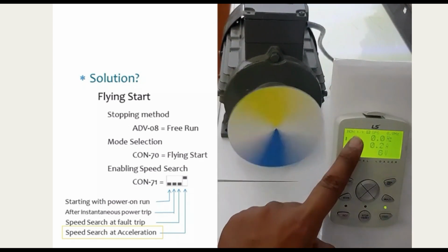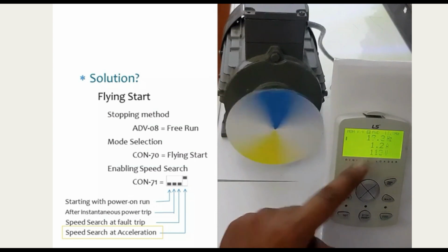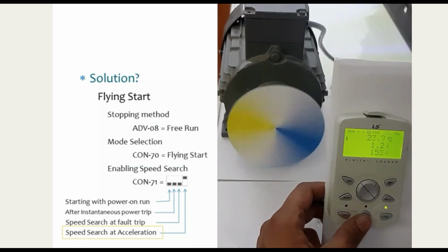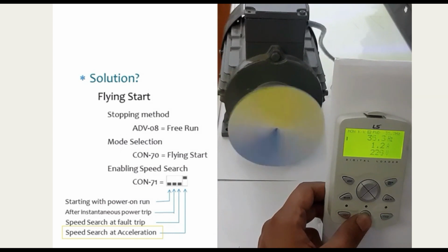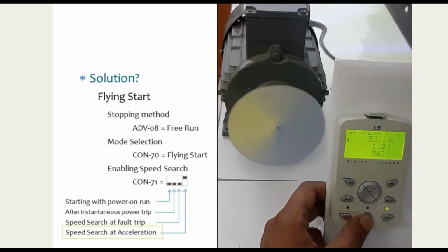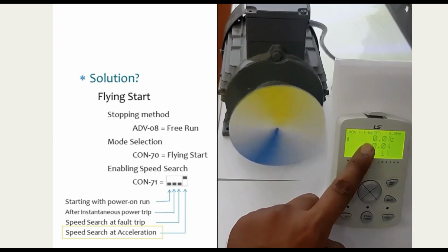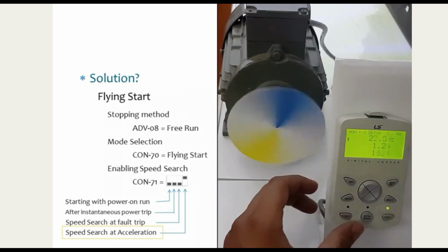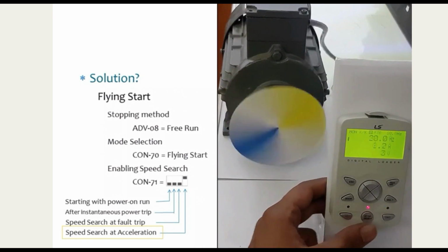Now let's start the motor. When it is near full speed, I have given the off command. The shaft is rotating based on its momentum, and look, it estimated and got the right speed to start.